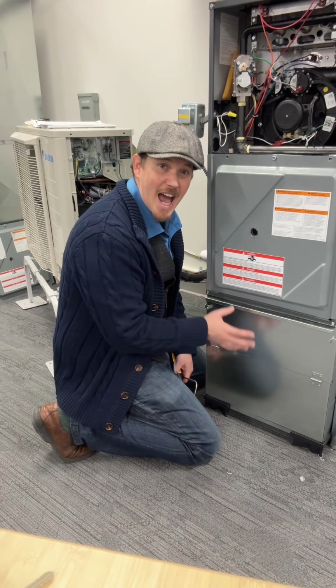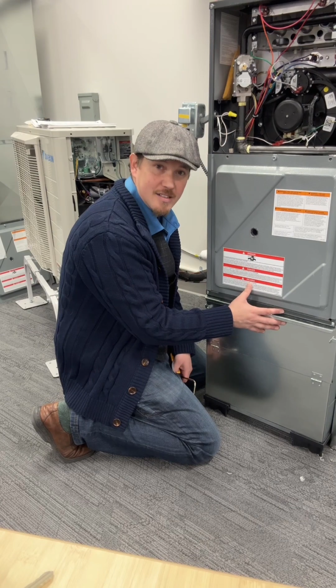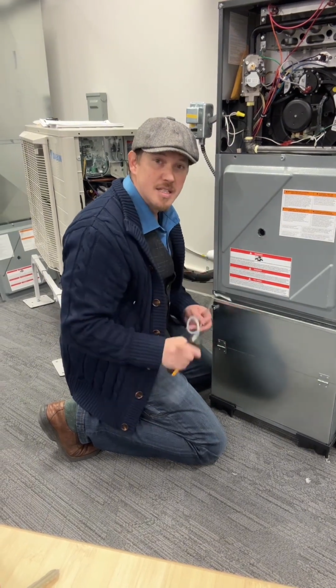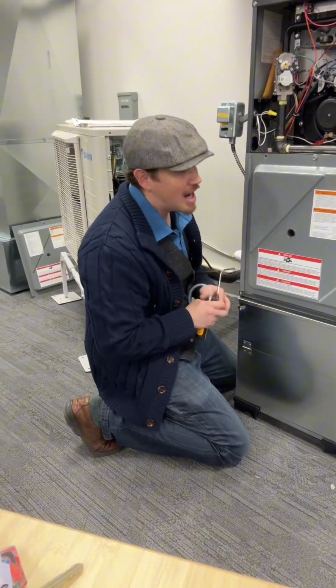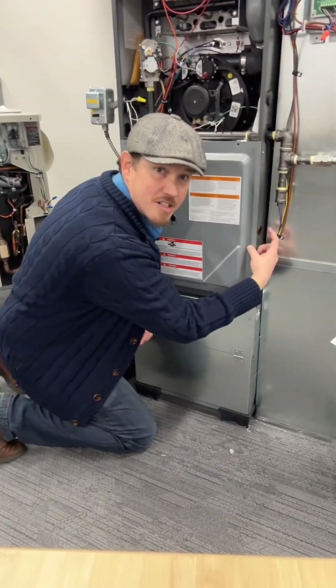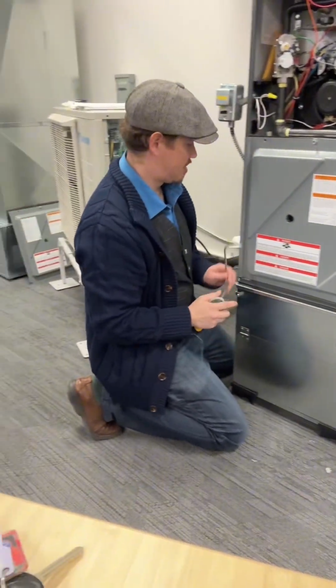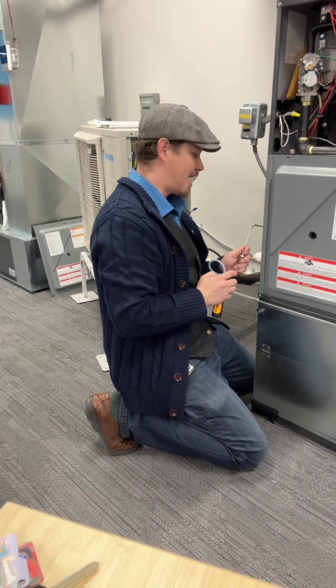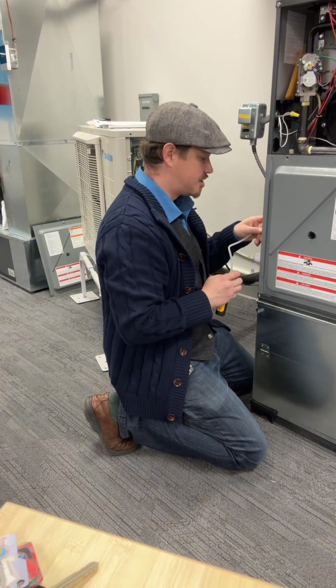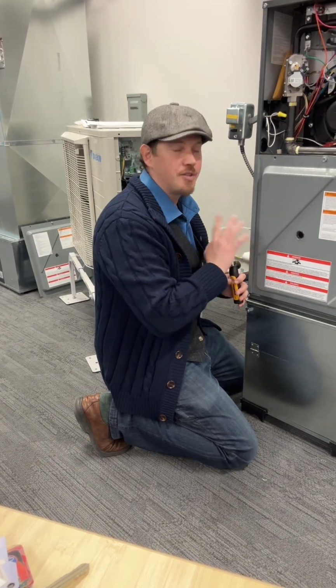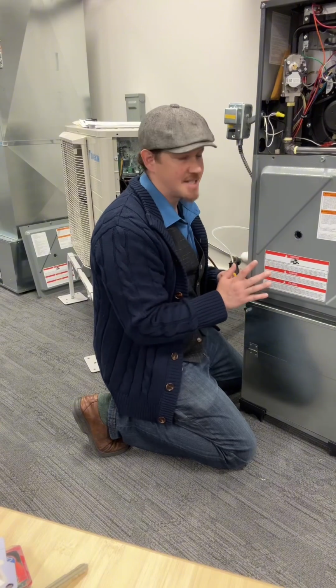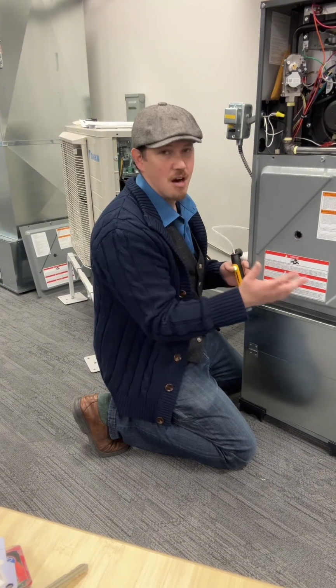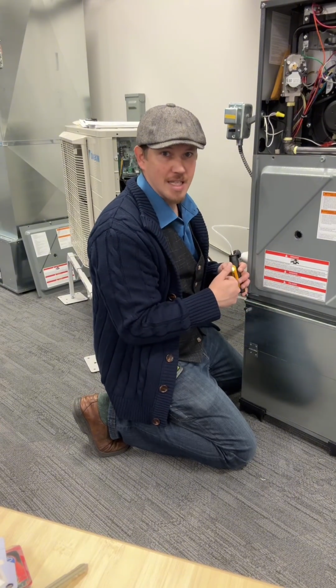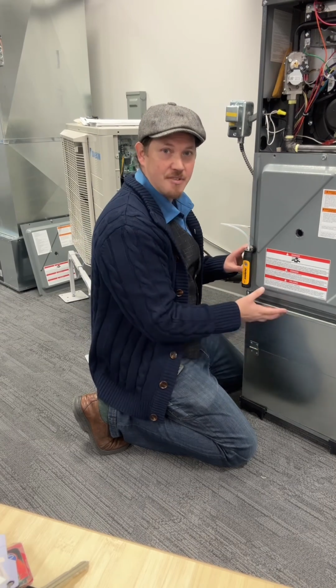And then I check after my filter, which is right here, before the blower. It's nice and easy on this. If you have a spot where all of your wires are going in, or in this case, it's on this side. With this, you gotta be careful that you're not hitting any of the electronics in here. The last thing you wanna do is zap yourself or fry a board just because you're trying to do the right thing. Now I'm checking after the filter.